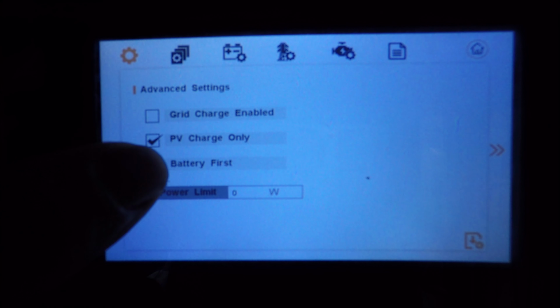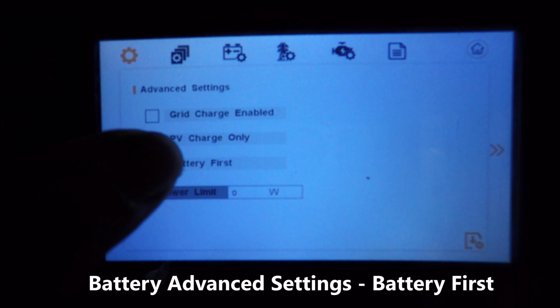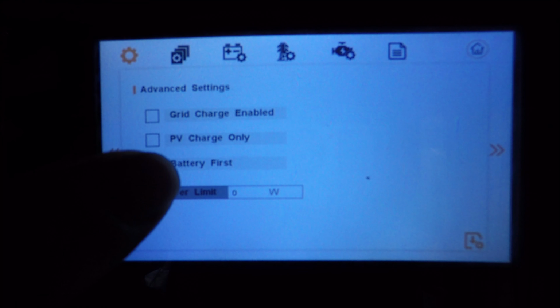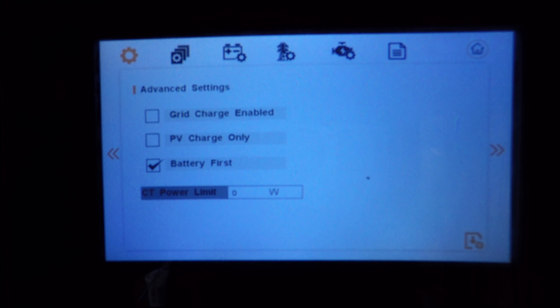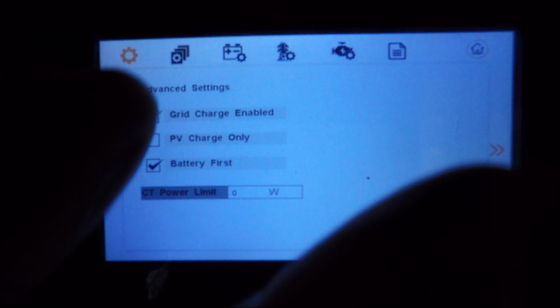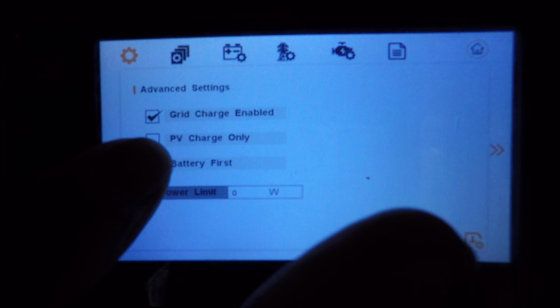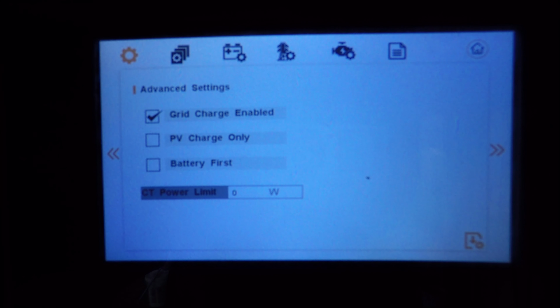We can also set it for PV charge only and battery first. As long as you have battery first selected, it will divert all power to charging the batteries first. Once the batteries are at 100%, then the inverter will power the loads. In my case, I want grid charged, and I want to allow the inverter to simply manage what gets charged and what gets powered with whatever the input is coming in from the solar, the battery, or the grid.